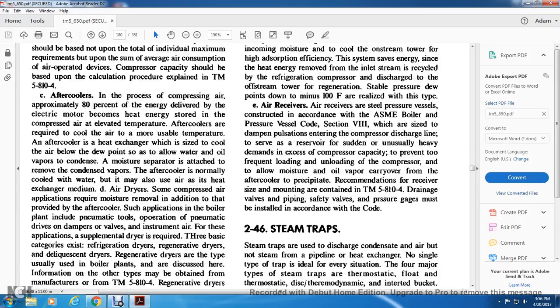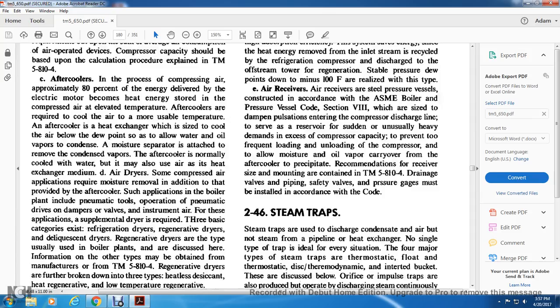The air receiver. Air receivers are steel pressure vessels constructed in accordance with the ASME Boiler and Pressure Vessel Code, Section 8. They are sized to dampen the pulsation entering the compressor discharge lines, to serve sudden unusual heavy demands in excess of compressor capacity, to prevent frequent loading and unloading of the compressor, and to allow the moisture and oil vapor carried from the aftercooler to precipitate. The recommendations for receiver sizing are in TM 5-810-4. Drainage valves, piping, safety valves, and pressure gauges must be installed in accordance with the code.